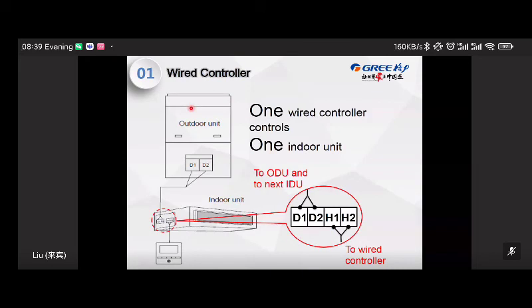So the previous pages, there are some introduction of the icons. So when you do the wiring of the controller, there are many choices, such as one wired controller controlling one indoor unit, as shown on this slide. This is the basic wiring method, one to one. H1, H2 terminal, this is for the wired controller.